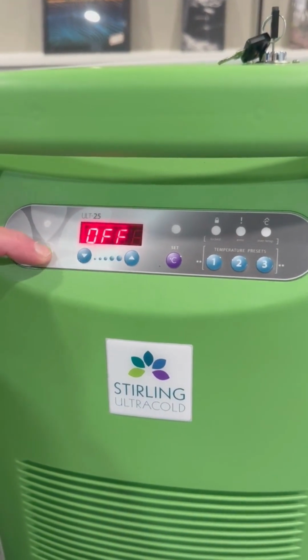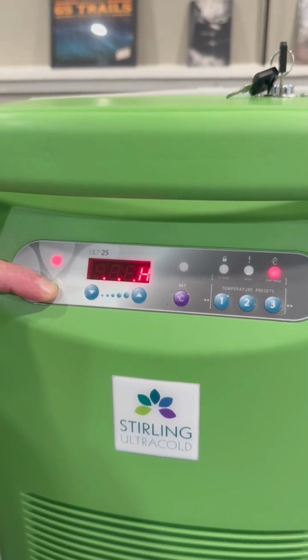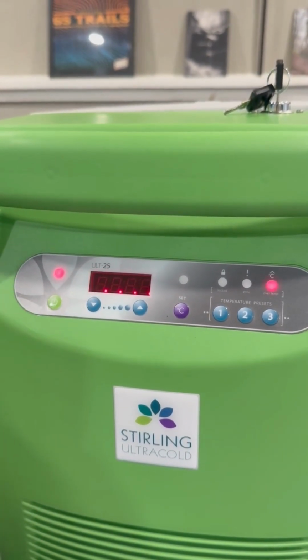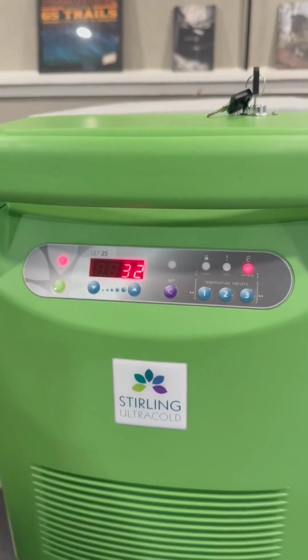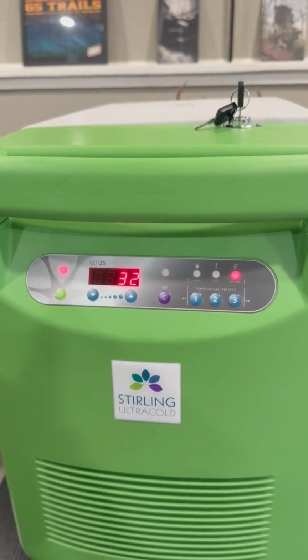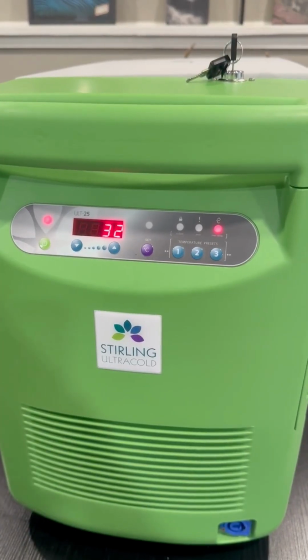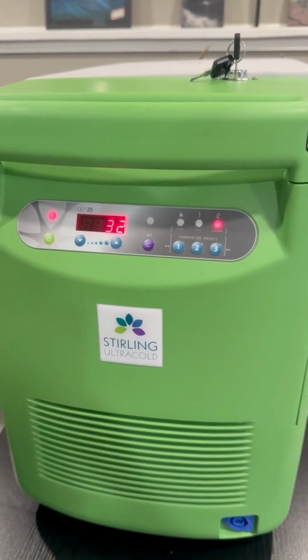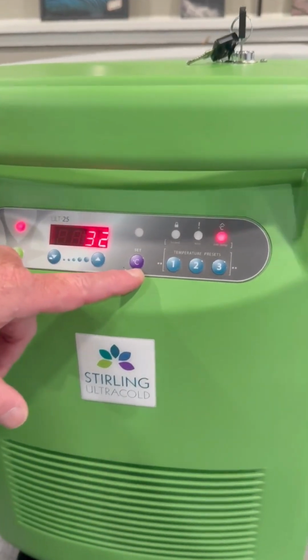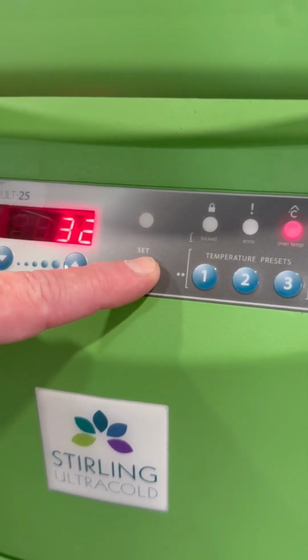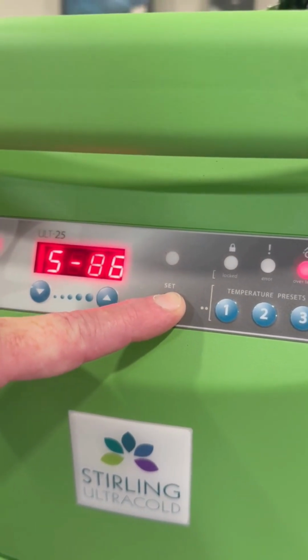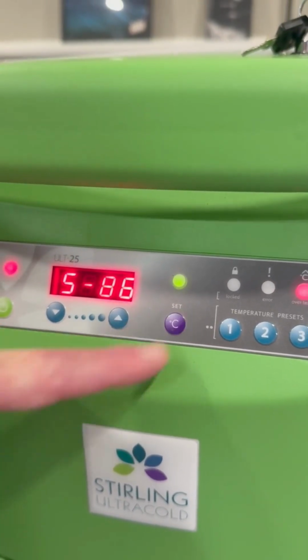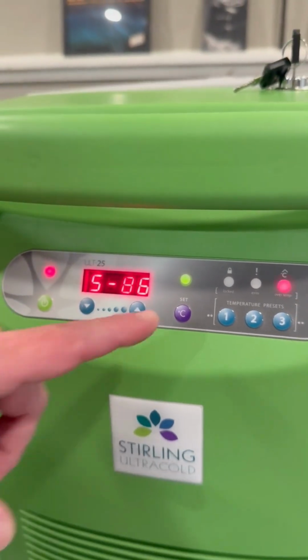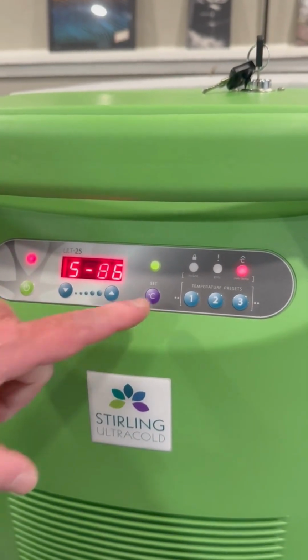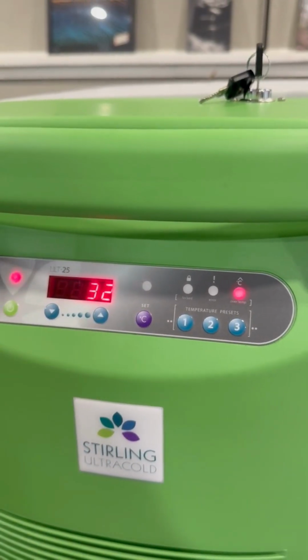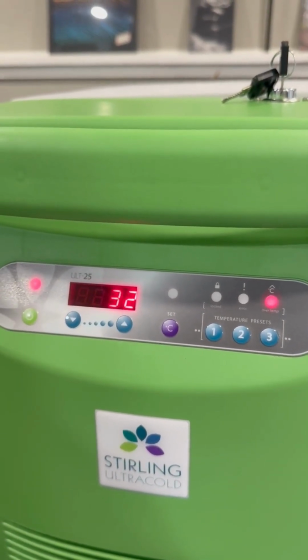This is going to display your temperature at all times. So we're going to turn the unit back on, and it is now powered back on, and you are seeing the ambient temperature where we just plugged it in out of the box. To display the temperature set point, you are going to want to hit the letter C, which is right here. It is the purple button. Whenever you hit the letter C, it will show you what the freezer set point is. This freezer is set at negative 86 degrees Celsius. If you want to see what the temperature of the unit currently is, hit the C again, and it will tell you it is now at 32 degrees Celsius ambient temperature.